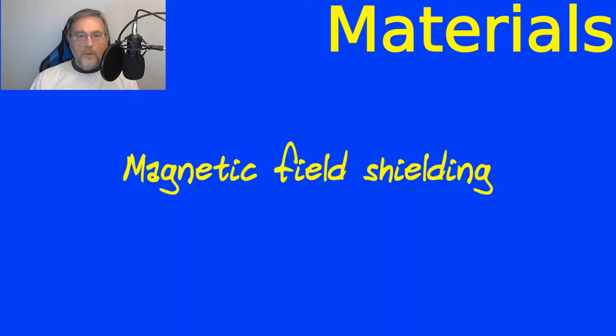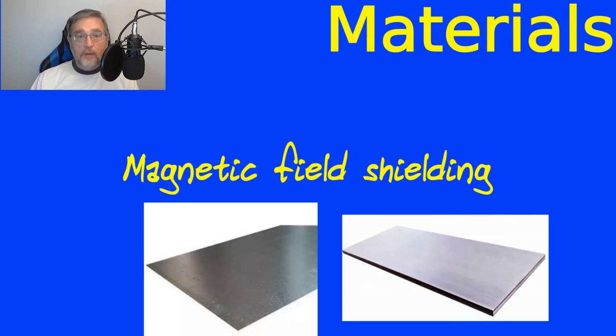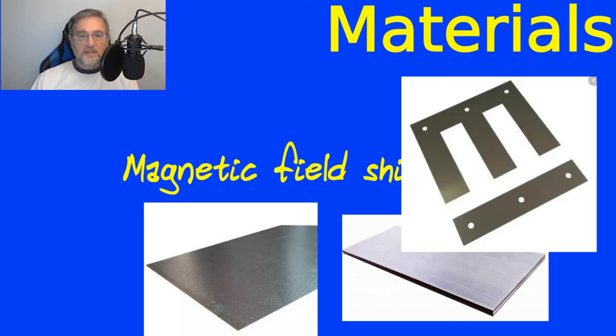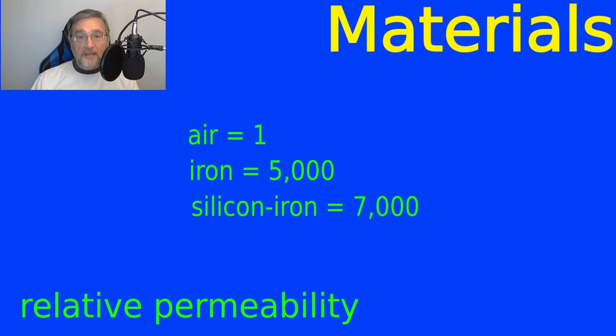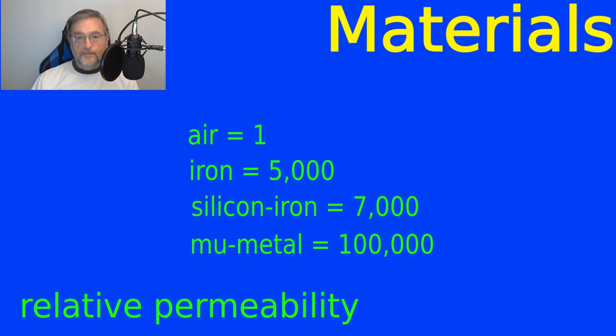To shield from magnetic fields, we need to use a material that is permeable to magnetic fields. Iron and steel are the obvious examples, but there are some alloys that are particularly good for magnetic shielding, like silicon iron and mu metal. Just to give you an idea, the relative permeability of air is defined as 1. Iron with 0.2% impurities has a relative permeability of 5,000. Silicon iron has a permeability of 7,000. Mu metal has a permeability of 100,000. Depending on how thick we can make the shield and the amount of magnetic energy we want to stop, we choose one solution over the other.